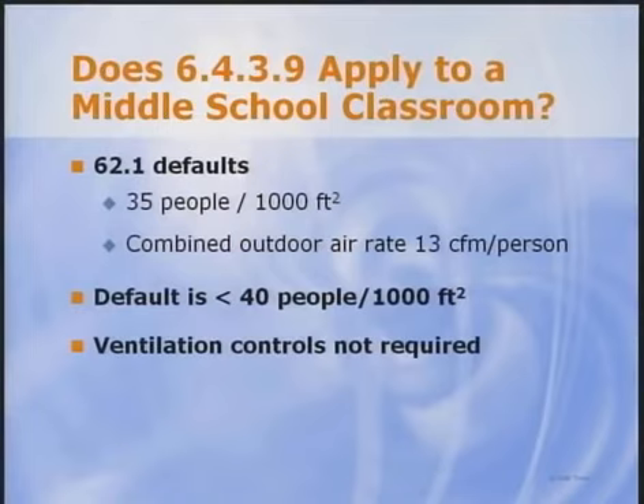ASHRAE 62.1 gives default values for the number of people per 1,000 square feet. These are only to be used if you don't know the occupancy of a particular space. In the case of a middle school classroom, the default is 35 people per 1,000 square feet. This is lower than 40 people per 1,000 square feet, so this is not considered a high occupancy area. Dennis has put other examples into the written newsletter.